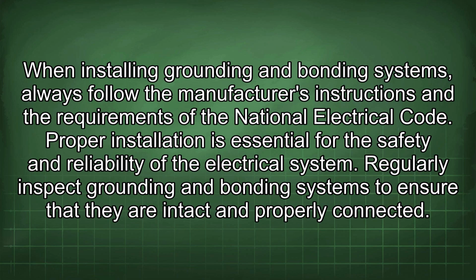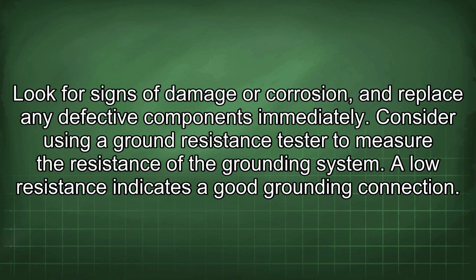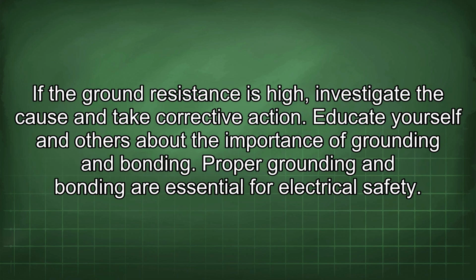When installing grounding and bonding systems, always follow the manufacturer's instructions and the requirements of the National Electrical Code. Proper installation is essential for the safety and reliability of the electrical system. Regularly inspect grounding and bonding systems to ensure that they are intact and properly connected. Look for signs of damage or corrosion and replace any defective components immediately. Consider using a ground resistance tester to measure the resistance of the grounding system. A low resistance indicates a good grounding connection. If the ground resistance is high, investigate the cause and take corrective action.